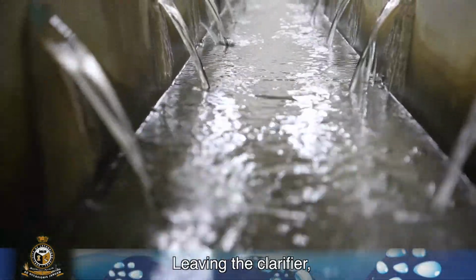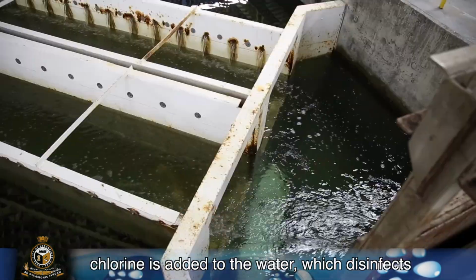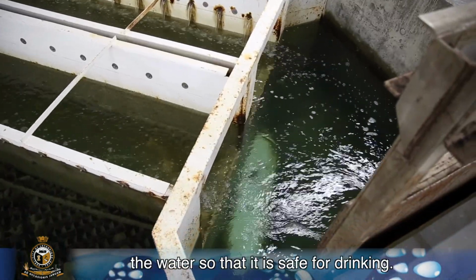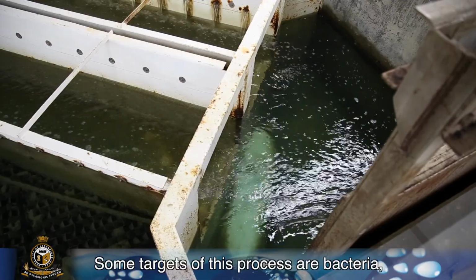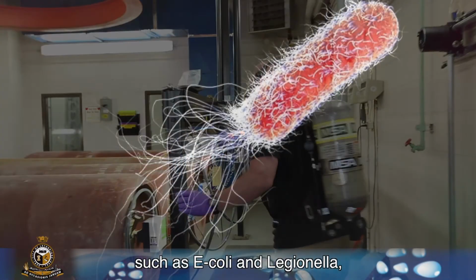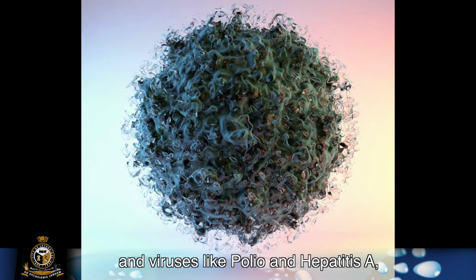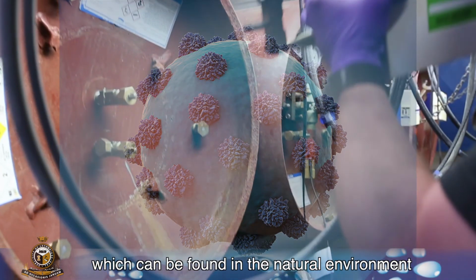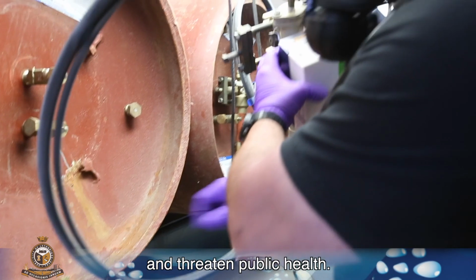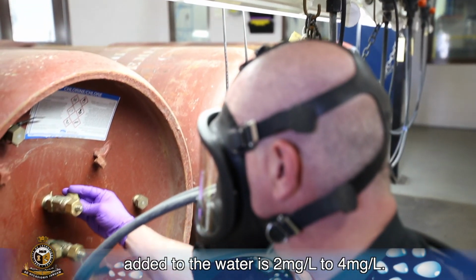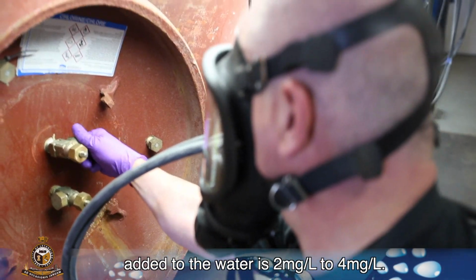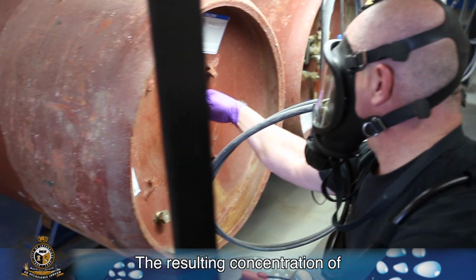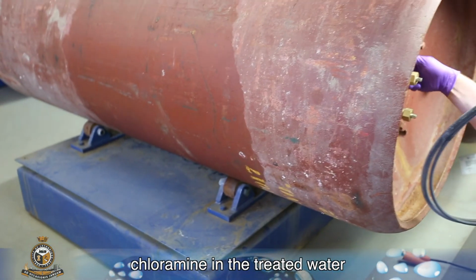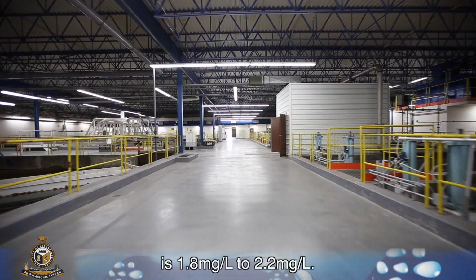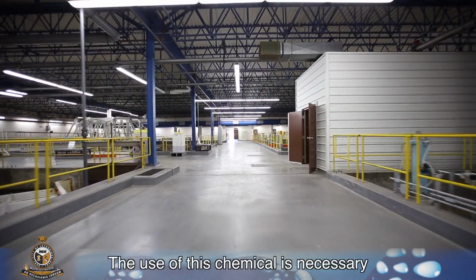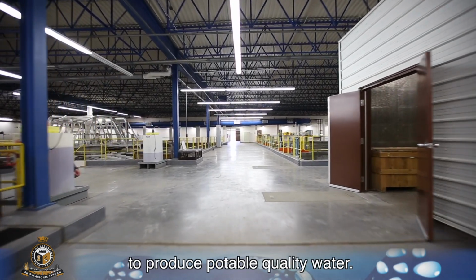Leaving the clarifier, chlorine is added to the water, which disinfects the water so that it is safe for drinking. Some targets of this process are bacteria, such as E. coli and Legionella, and viruses like polio and hepatitis A, which can be found in the natural environment and threaten public health. The dosage of chlorine added to the water is 2 milligrams per liter to 4 milligrams per liter. The resulting concentration of chloramine in the treated water is 1.8 milligrams per liter to 2.2 milligrams per liter. The use of this chemical is necessary to produce potable quality water.